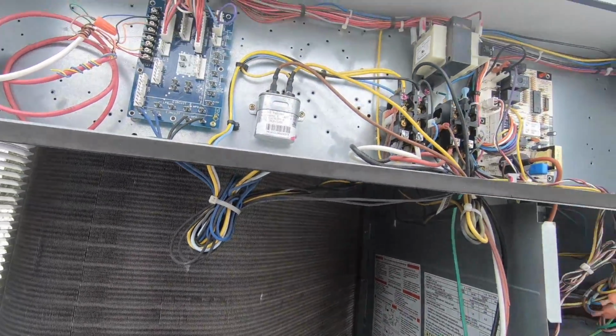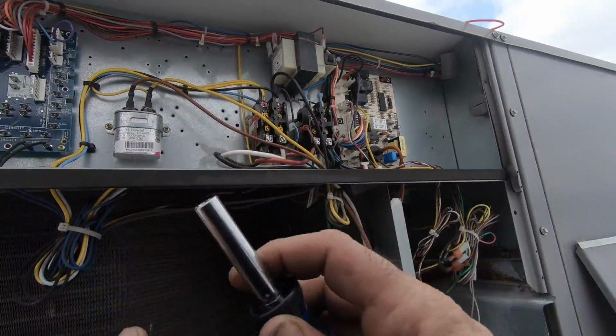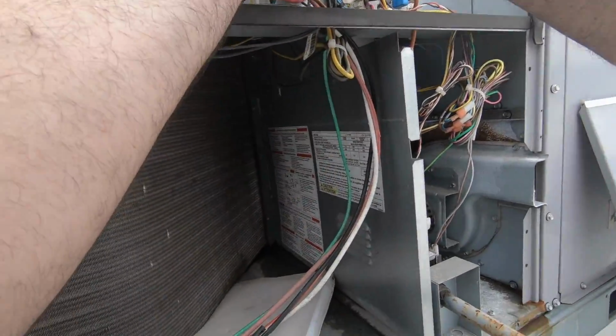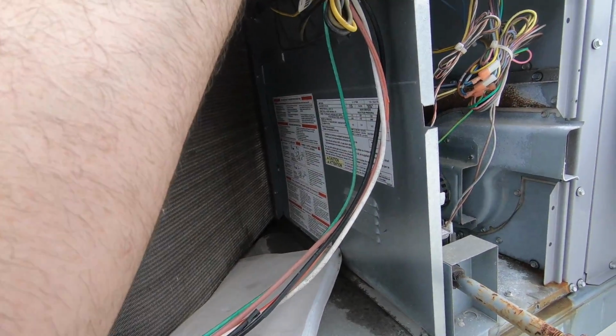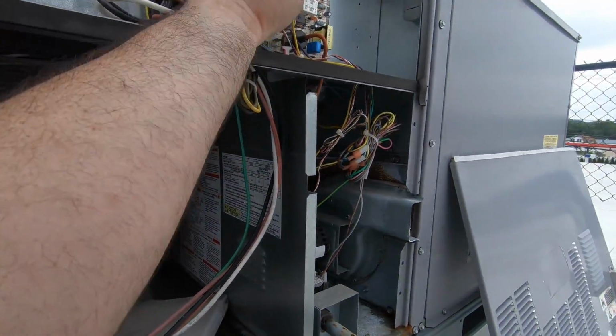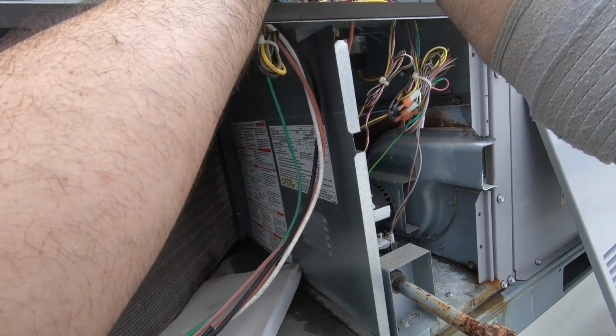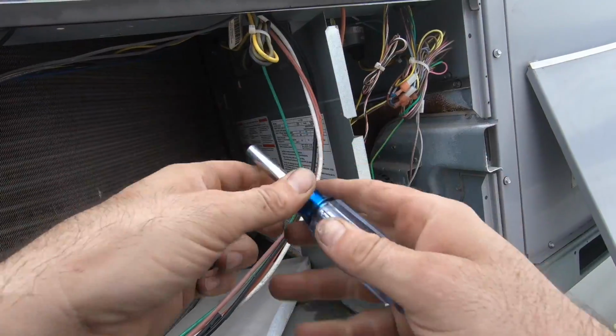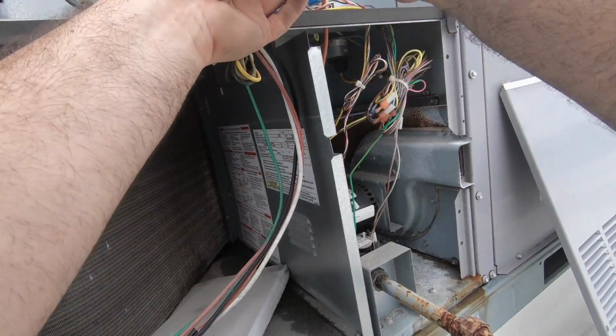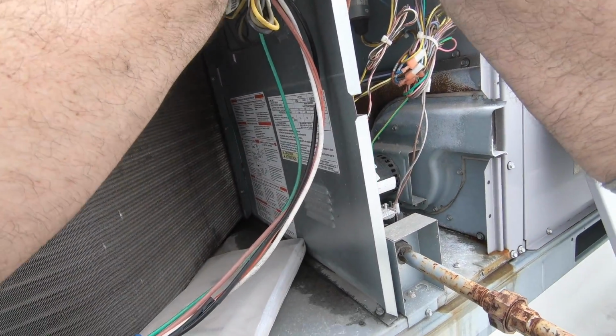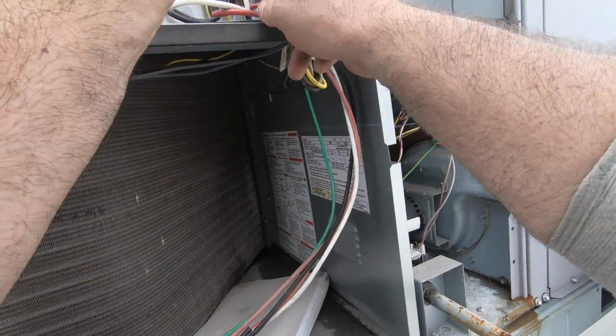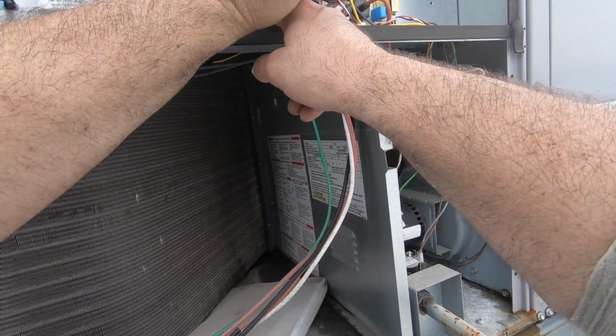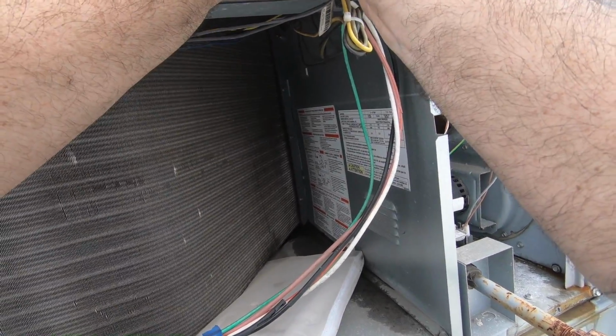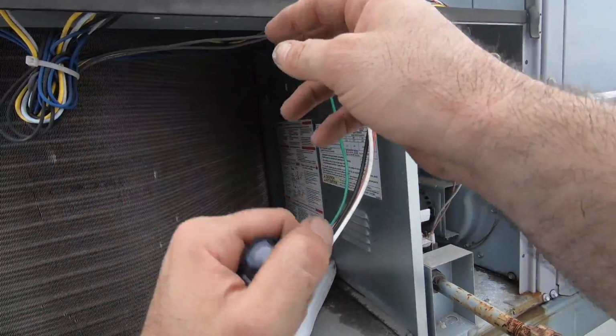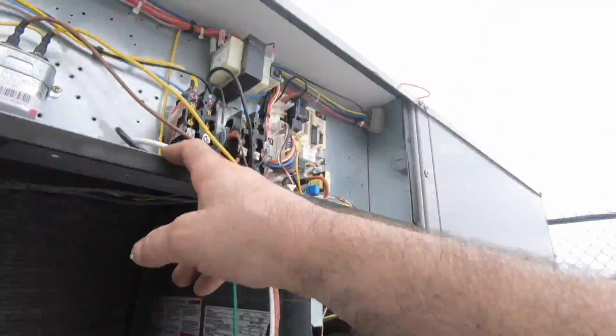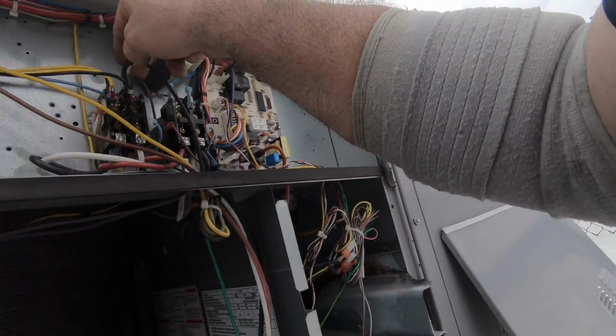Let's just quickly check. Find my 5/16, it's perfect without breaking anything on most contactors. And I know guys, they want to kill everything. Like, this doesn't even have anything attached to it, so it doesn't matter. No reason to kill everything, because here's the thing: if you keep tightening this and tightening this, know your torque, because what happens if you gotta change it and you over torque it? I guess, well, we could always cut, but make sure all your stake-ons are slid on correctly, nothing's loose.